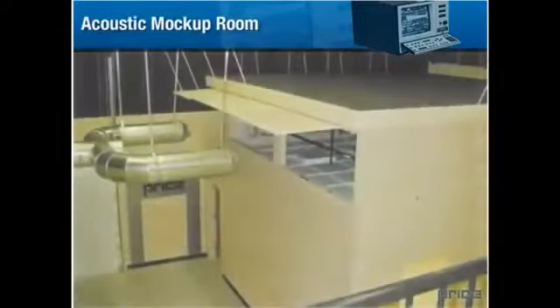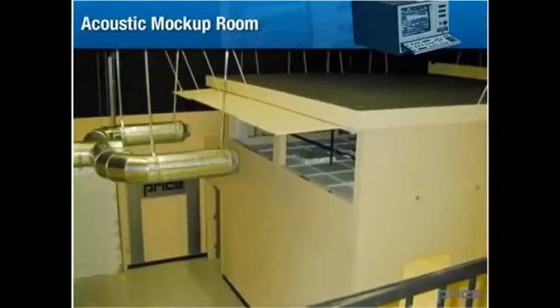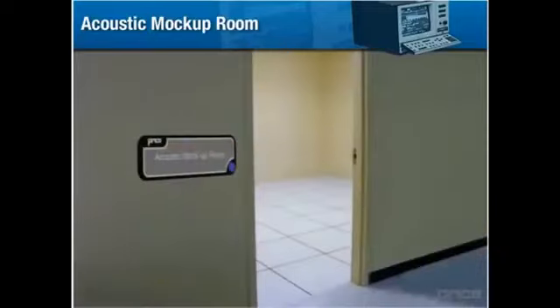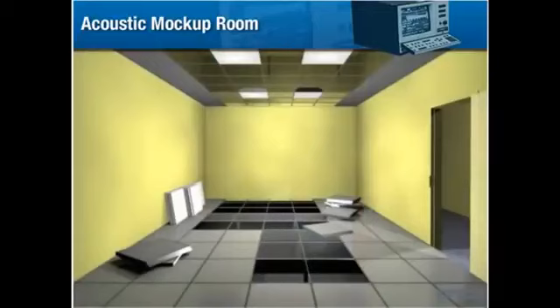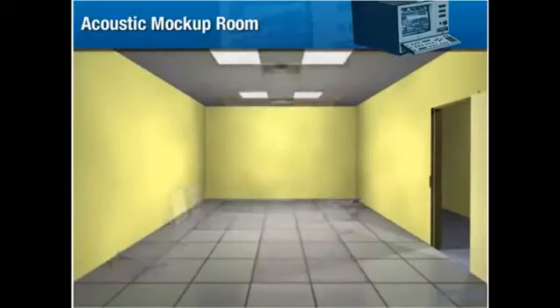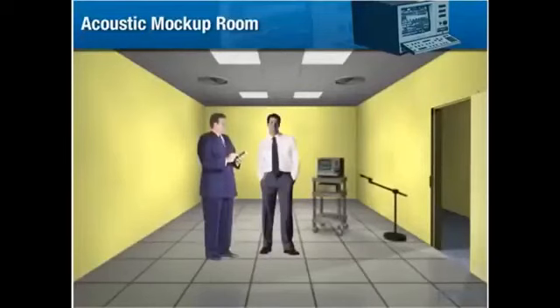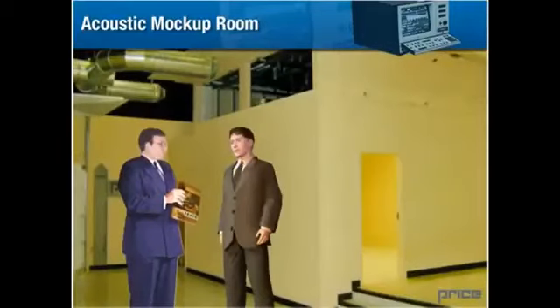Acoustic mock-up room. In order to demonstrate and experience real-world scenarios, Price has constructed a test room specifically for conducting acoustic mock-up tests for terminal units. The room has been designed and finished in accordance with Acoustical Consultants Guidelines for simulating actual office acoustics. Mock-ups can be developed for each project's unique specifications, including terminal unit type, size, air volume, ceiling construction, etc. Acoustic mock-up tests are a very effective method of verifying room NC levels as opposed to relying on the theoretical calculations for terminal unit applications. Visitors can listen to the system in operation as well as be provided with sound measurements.